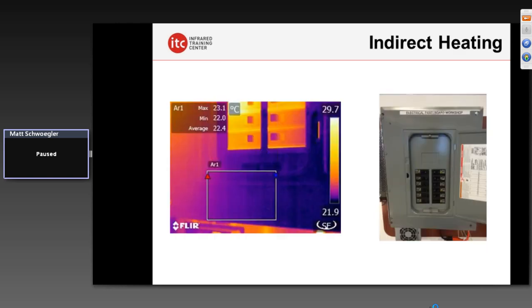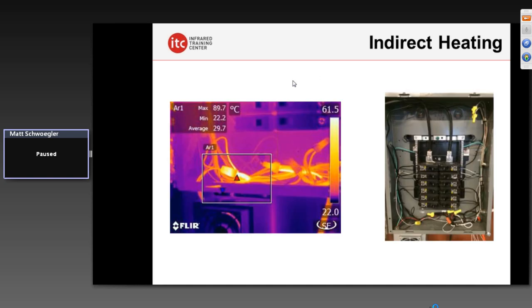Check out this small panel board we have in our lab. On the outside you can see the surface temperature of the box — about 22 degrees Celsius, around 74-75 Fahrenheit. You don't really see much at all. If I take that cover off, there's a connection inside that's well over — look at that, 89 degrees — that's the maximum temperature on that connection. That's a very significant problem if you were to find it in the field. But you need that direct line of sight to see that.